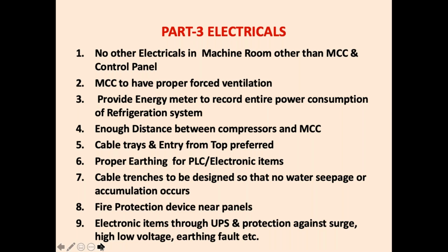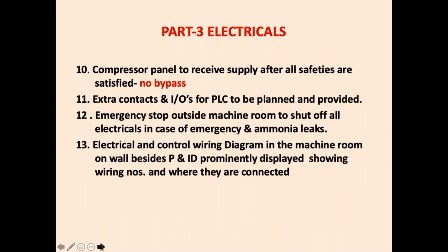So proper earthing for electronic items, electrical items, PLCs is very, very important. Cable trenches to be designed so that no water accumulates. Fire protection devices very near to the panels are essential in case of electrical problems. Electronic items through UPS and protections should be against surge, high voltage, earthing faults, etc. So these are the electrical issues.